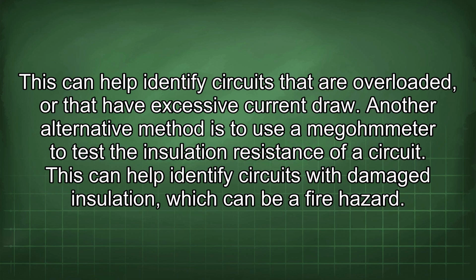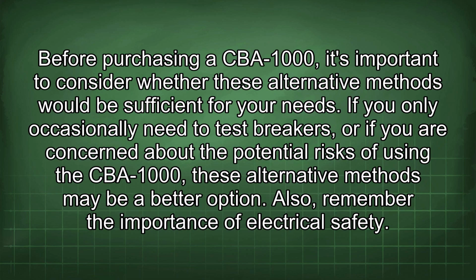Another alternative method is to use a megohmmeter to test the insulation resistance of a circuit. This can help identify circuits with damaged insulation, which can be a fire hazard. Before purchasing a CBA-1000, it's important to consider whether these alternative methods would be sufficient for your needs. If you only occasionally need to test breakers, or if you are concerned about the potential risks of using the CBA-1000, these alternative methods may be a better option.